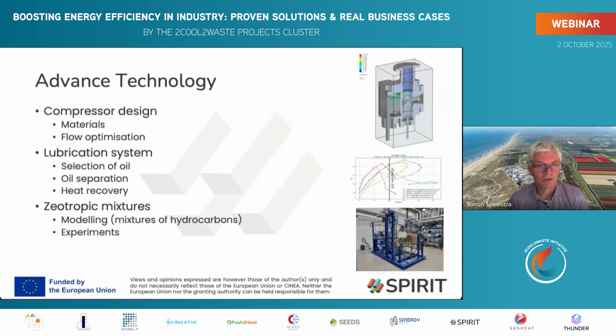Some technology development we do in parallel with the demos: we've been looking at compressors, mainly screw and piston compressors, examining materials, seals and oil to see whether they're suitable for the high temperature and pressure conditions in these heat pumps, and doing flow optimization studies for the piston compressor to redesign the flow geometry for less pressure drop and higher efficiency.